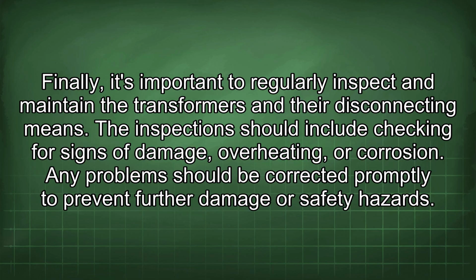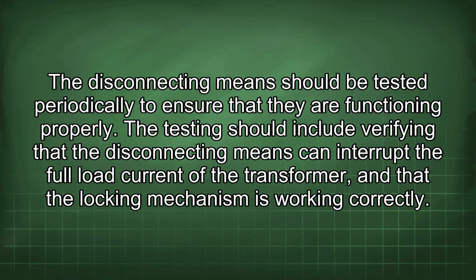Finally, it's important to regularly inspect and maintain the transformers and their disconnecting means. The inspection should include checking for signs of damage, overheating, or corrosion. Any problems should be corrected promptly to prevent further damage or safety hazards. The disconnecting means should be tested periodically to ensure that they are functioning properly.